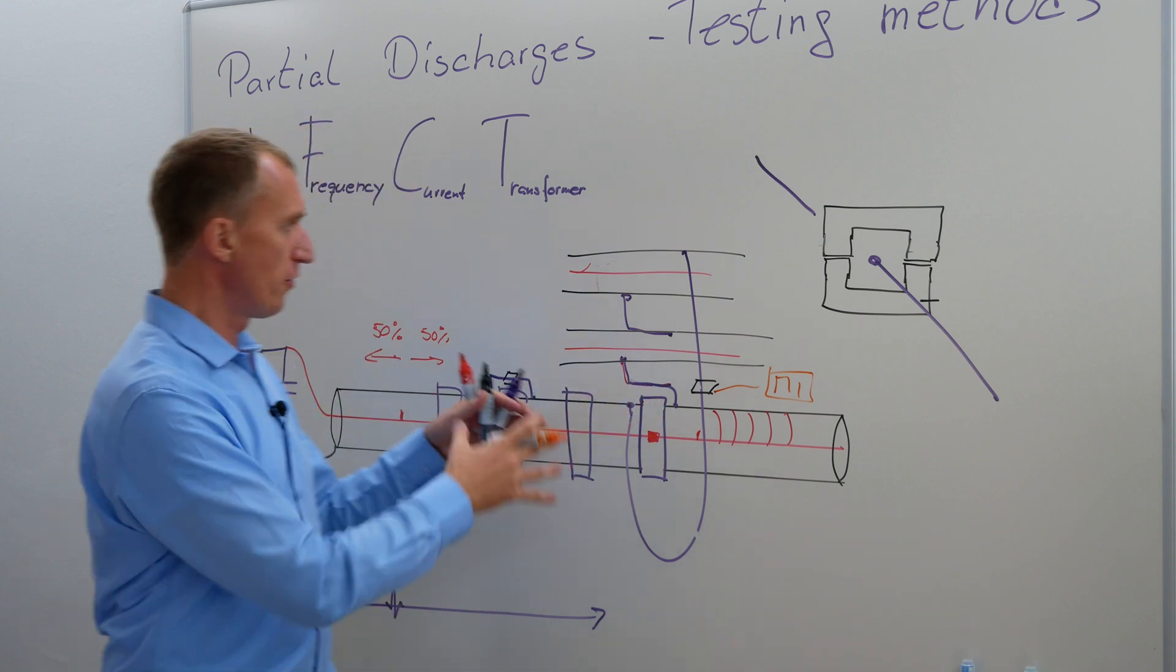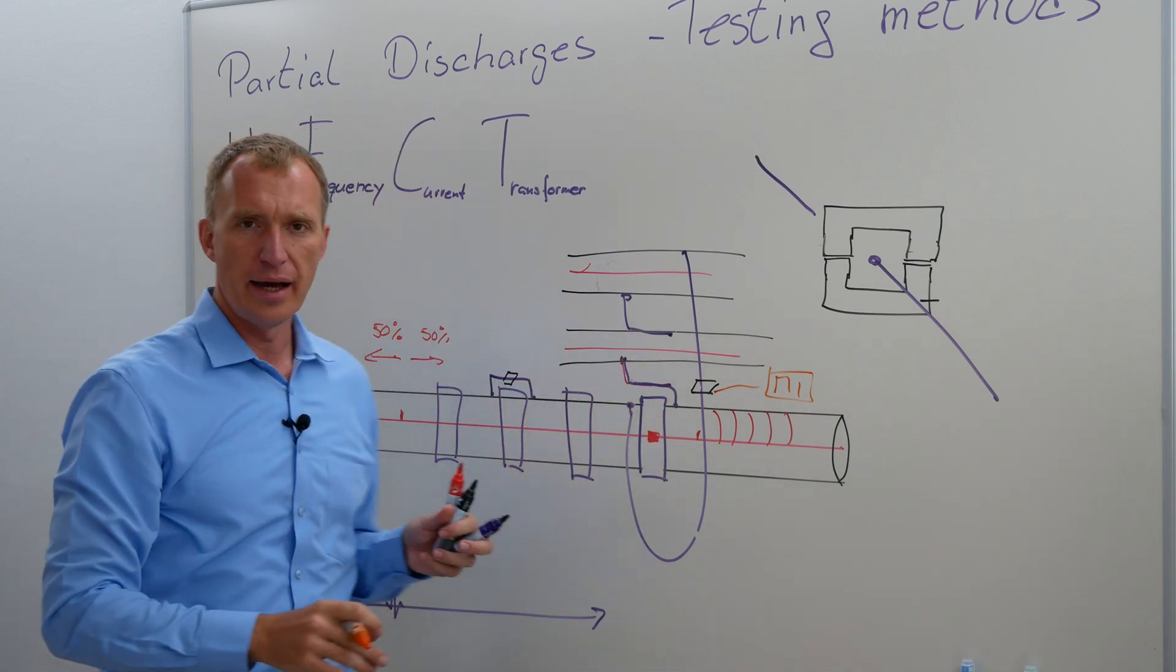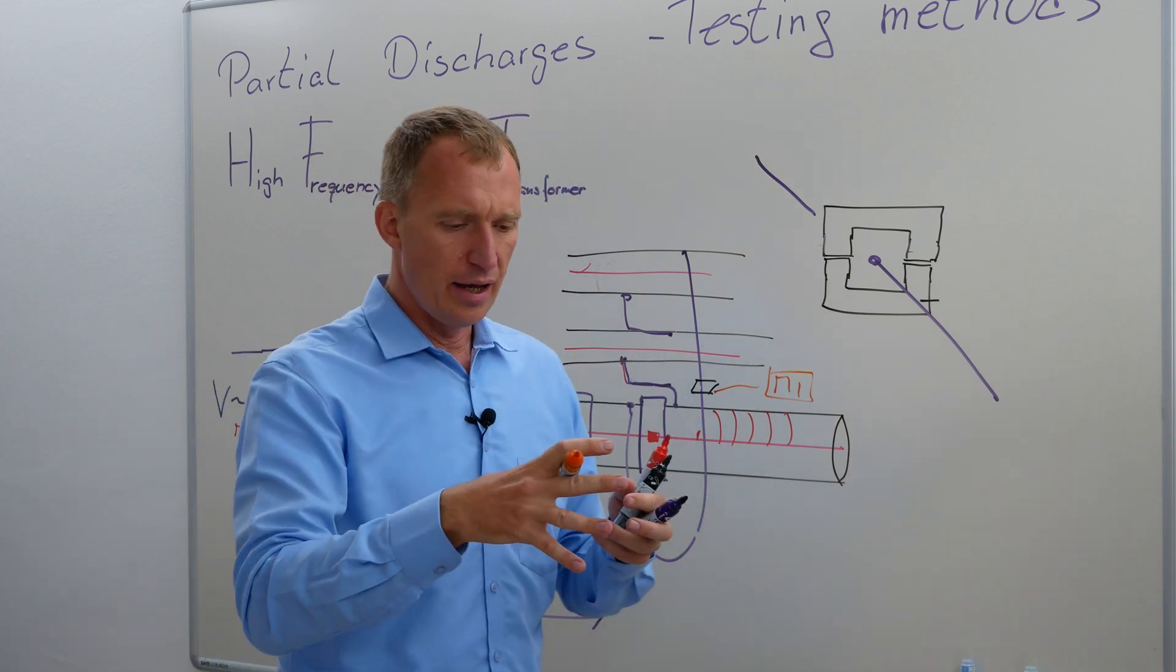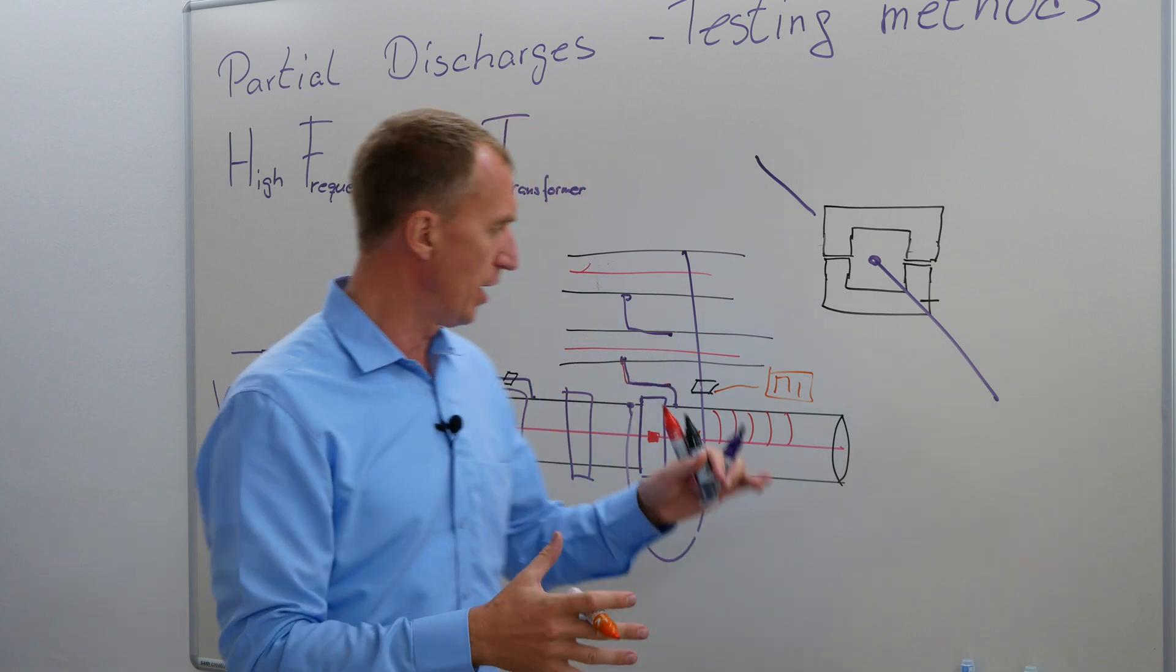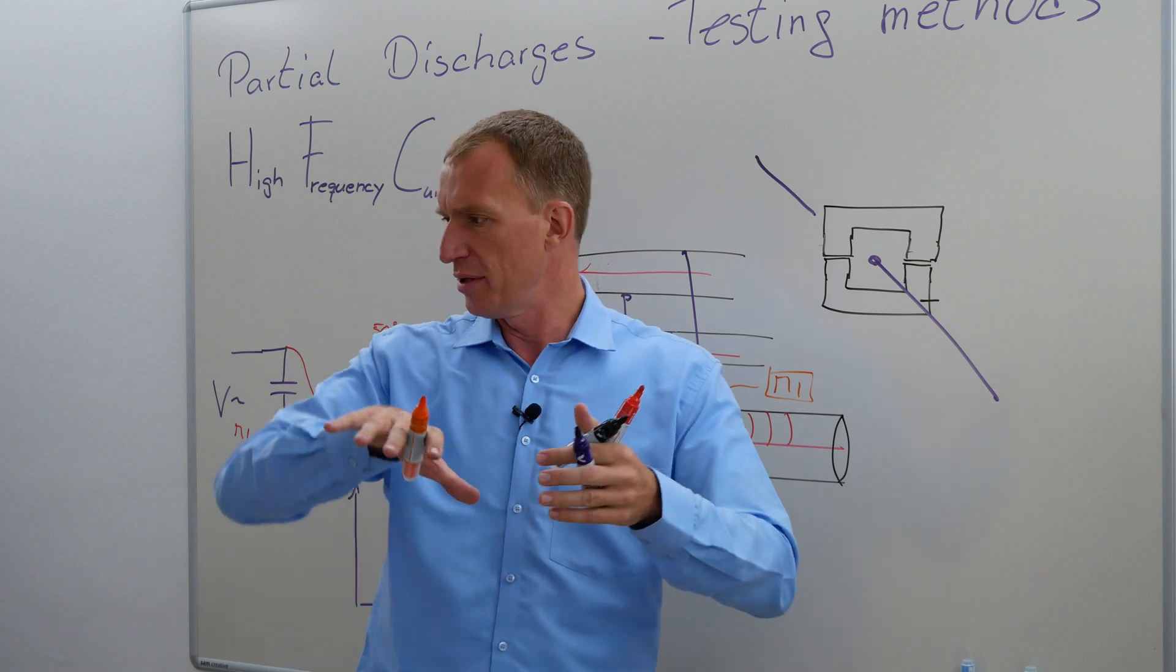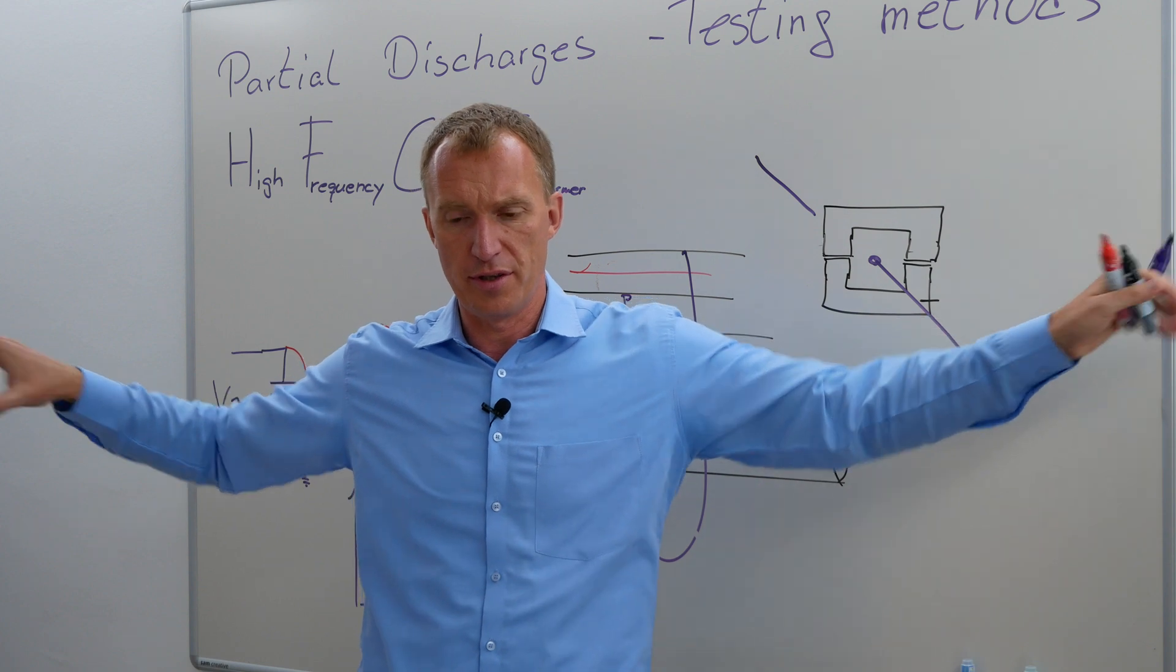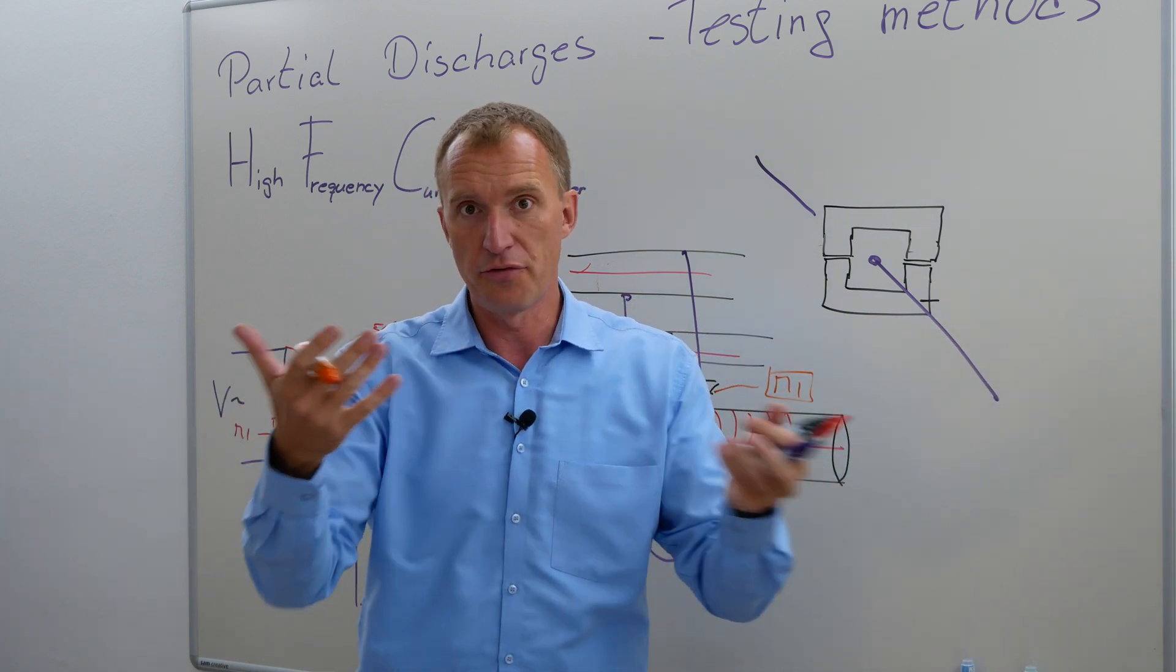You're able to measure on a very long cable, 20 kilometers. You can measure more or less localized. And now you can play around a little bit of the frequency in order to figure out how far can I see. So I'll give an example. If you're measuring the low frequency and you're having one of these HFCTs here, it is not uncommon that you can measure one kilometer or two kilometers on this side and two kilometers on this side. Meaning, you see multiple joints.